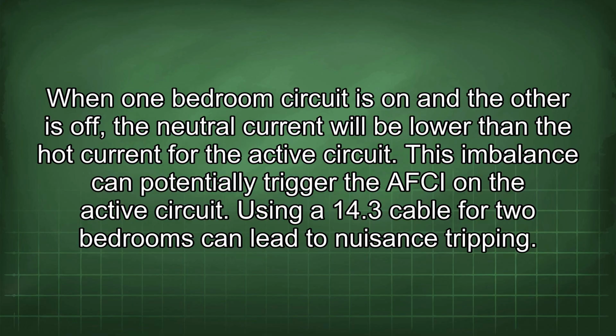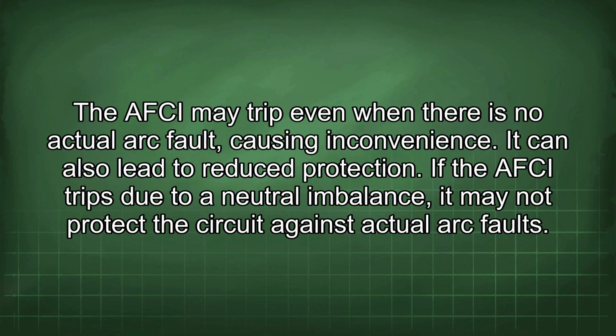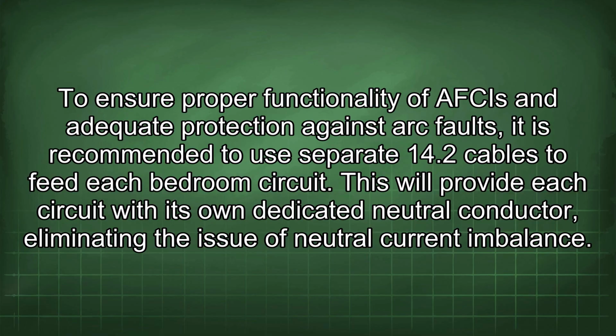Using a 14/3 cable for 2 bedrooms can lead to nuisance tripping. The AFCI may trip even when there is no actual arc fault, causing inconvenience. It can also lead to reduced protection. If the AFCI trips due to a neutral imbalance, it may not protect the circuit against actual arc faults. To ensure proper functionality of AFCIs and adequate protection against arc faults, it is recommended to use separate 14/2 cables to feed each bedroom circuit. This will provide each circuit with its own dedicated neutral conductor, eliminating the issue of neutral current imbalance.